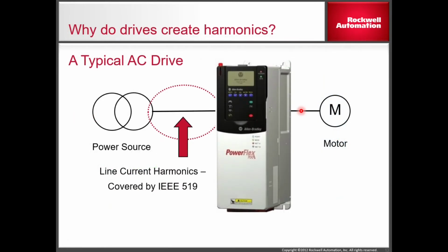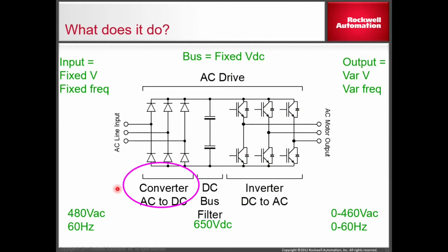So, why do my drives create harmonics? This little thing right here, this starts it all, the converter from AC to DC, which is needed. This is a 6-pulse diode bridge, which is basically in most 460 volt smaller PWM drives. And with that, you get the term 6-pulse, because each set of diodes makes 2 pulses onto the power system. So a 3-phase bridge is going to give you 6-pulse distortion on your system.